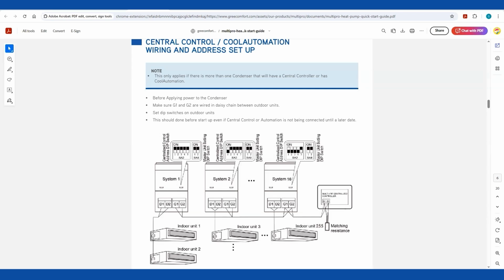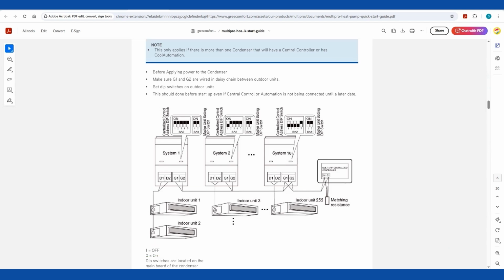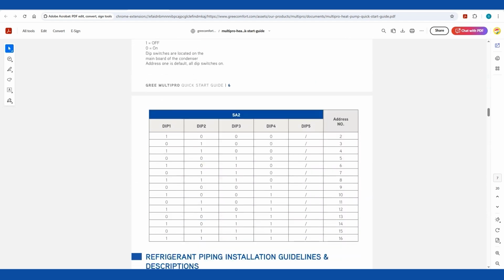That's why I'm telling you, just err on the side of caution, whether the customer wants it or not. Go ahead and hook up the G1 and G2 wiring, and then while the systems are still powered off, go in and set these unique addresses. So outdoor unit number 1, you don't set the dip switches. They're factory going to be all on.